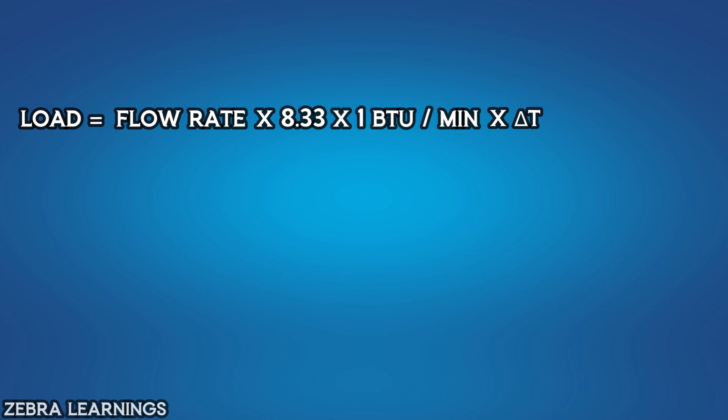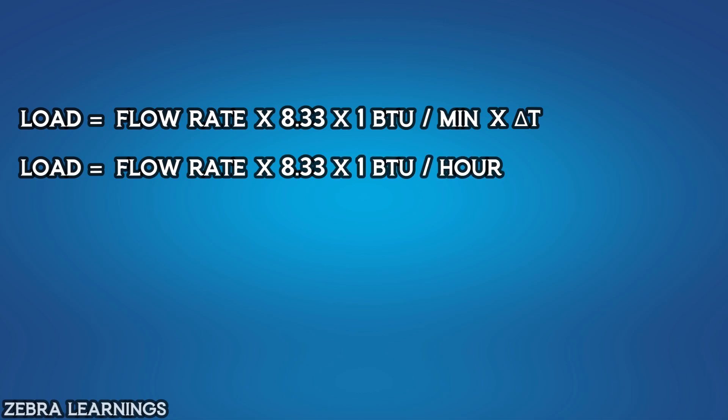In this, we need to convert minutes to hours. To convert from minutes to hours, we multiply by 60. So load equals flow rate multiply 8.33 multiply 1 BTU per hour multiply 60 multiply delta T.